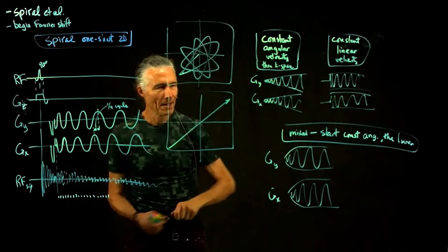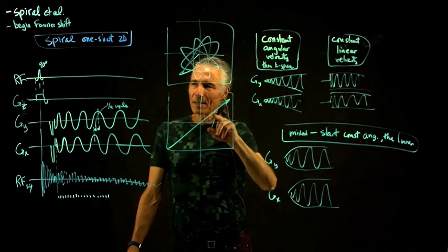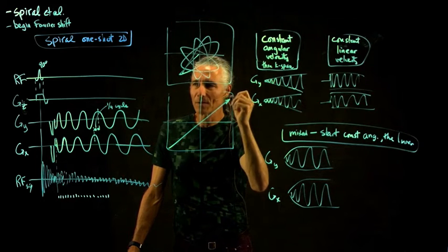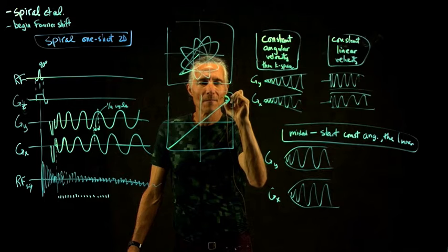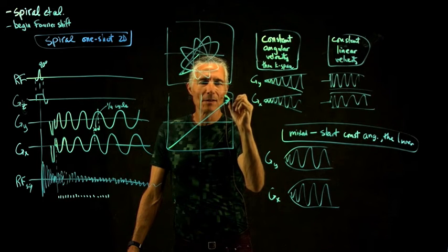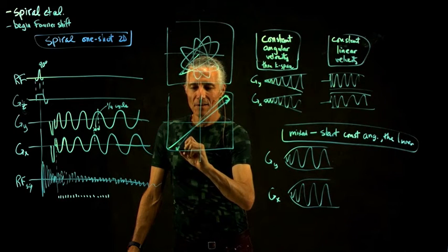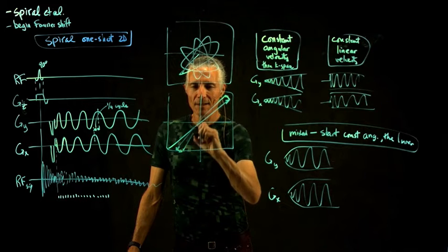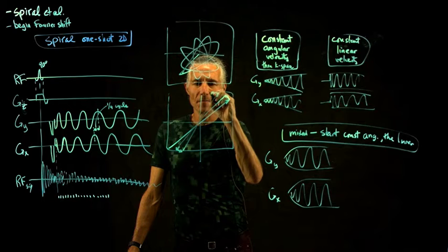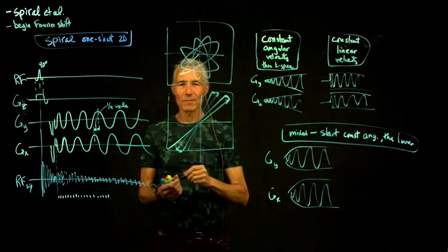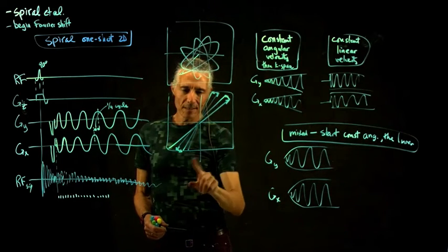This was by analogy with a CAT scan, and one of the guys who invented MRI originally did MRI this way. It's not commonly done anymore because there are various distortion problems with it. But the idea is you do something a little bit like echoplanar: go across K-space and then come across K-space again this way, then move a little bit and come across again, then move again. That way you have a lot of samples of the middle of K-space. That would be a radial passage through K-space. We can still do that on the scanner if you want.